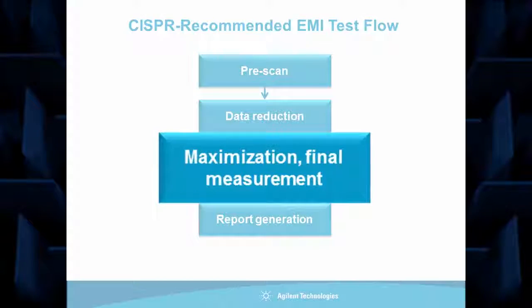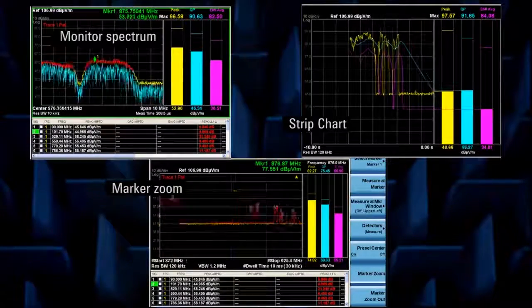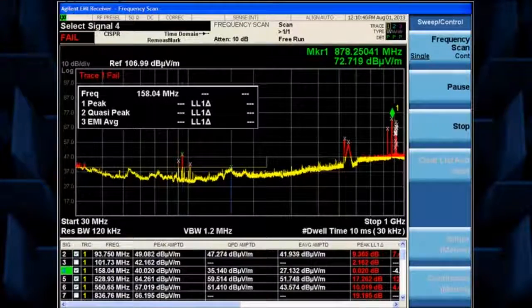Let's move on to signal maximization and the final measurement with EMI average and quasi-peak detectors for the signals in the list. Adjust frequency and amplitude as needed for maximization. Choose only the signals needed for final measurement.